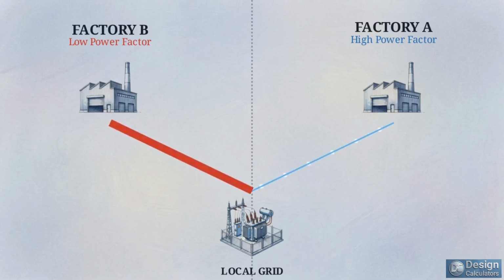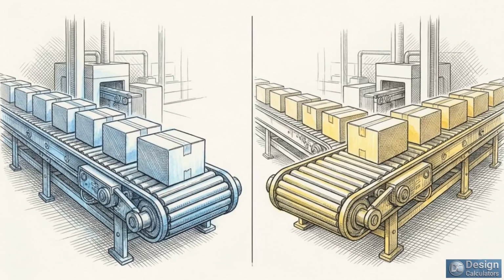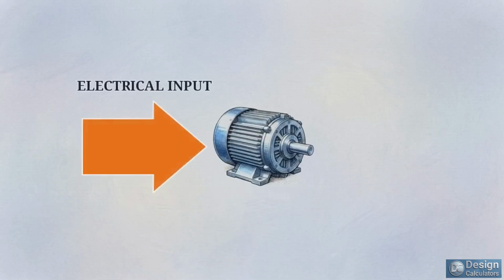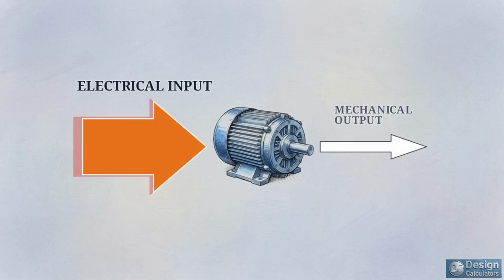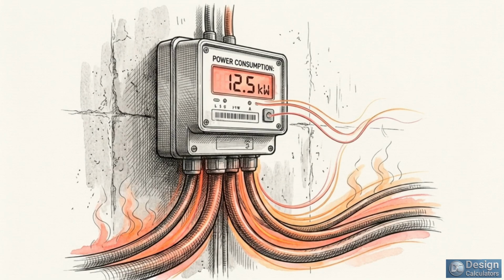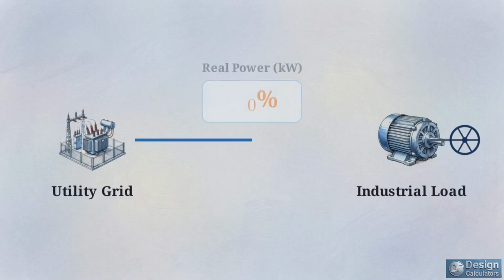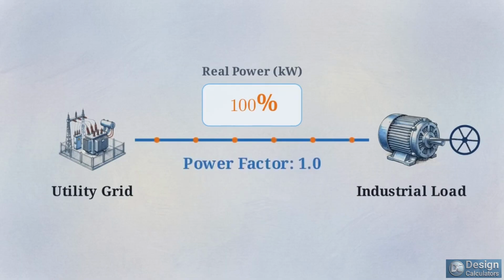Factory B is simply drawing significantly more electrical current from the local grid to perform the exact same work as Factory A. In industrial power systems, the mechanical output you get from a machine does not always equal the electrical input it demands. There is an invisible drain on the system. We usually assume that electricity pulled from a grid translates perfectly into mechanical motion. You plug a machine in and the motor spins.